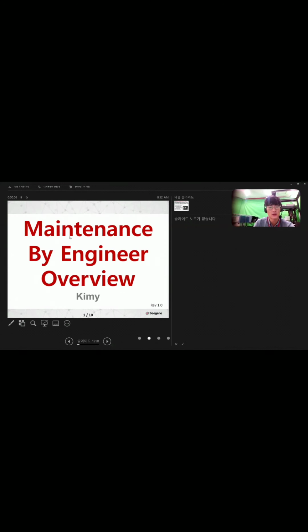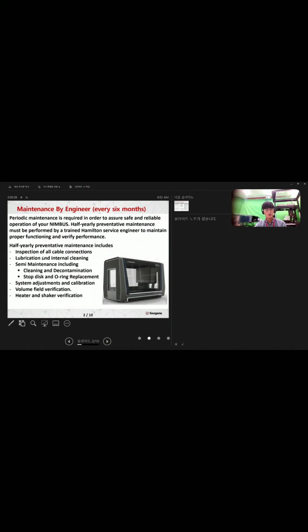Okay, we're going to learn about maintenance, which is preventive maintenance. Preventive maintenance is routine maintenance for the machine to keep it running and prevent any unplanned downtime from unexpected machine failure. Normally for the Nimbus, preventive maintenance is done twice a year. During that, the engineer has to inspect the cable, lubricate, and do the semi-maintenance. This includes replacement of the stop disc and O-ring. And after that, do some adjustment and calibration.